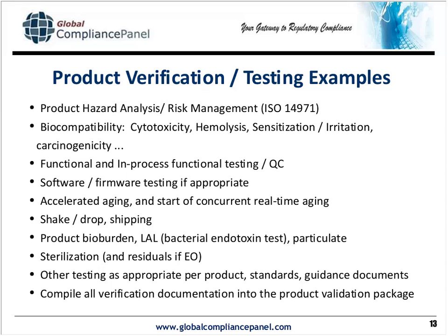So if you're claiming a 3-year shelf life, you should be pulling enough samples that you can check the sterility, if it's a sterile product, and the functionality of that product over its life, maybe each year, testing it up through the 3 or 5 year shelf life claimed. Shake and drop testing for packaging viability, as well as maybe real-time shipping across country or across the world, however you do that.